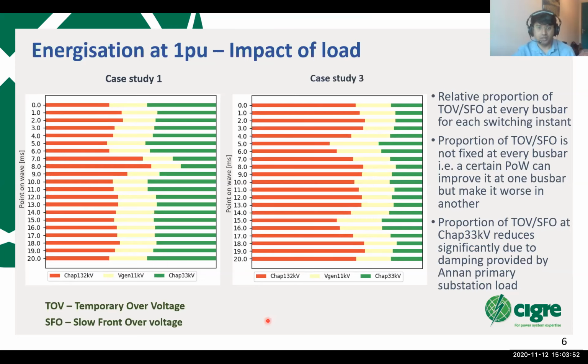That is what it means: a certain point on wave can improve the overvoltage or reduce the overvoltage at a bus bar, but another point on wave can actually make it worse. So the overvoltage is not a linear function of the point on wave across the network. So that's one thing.